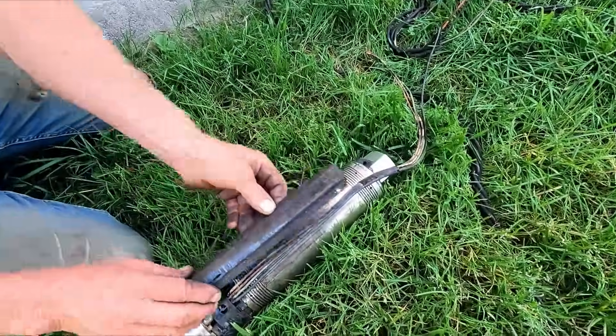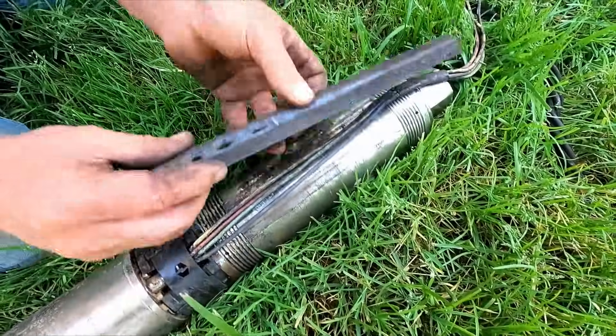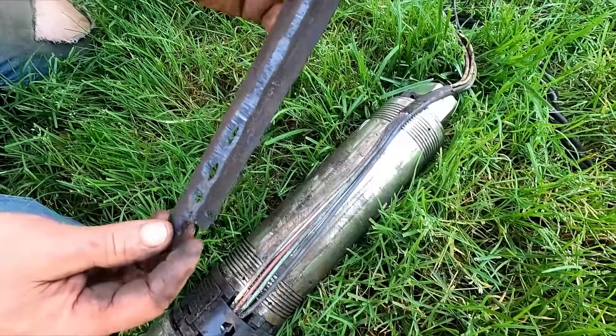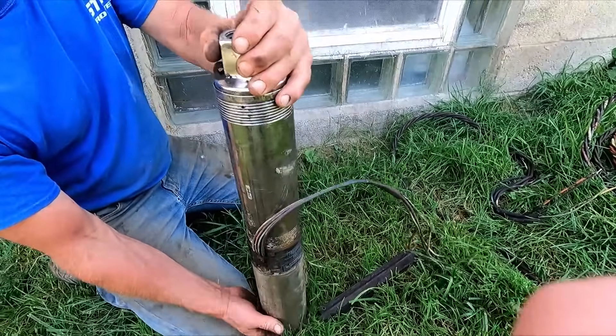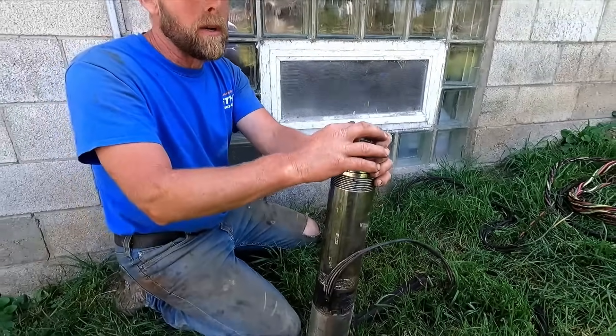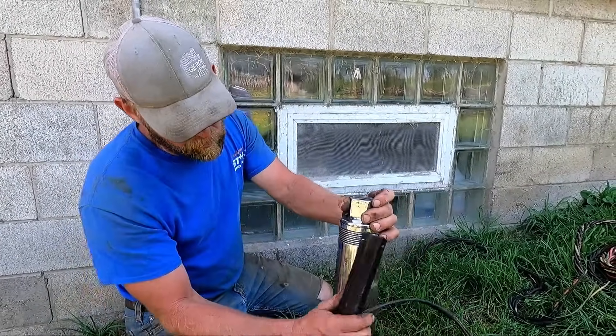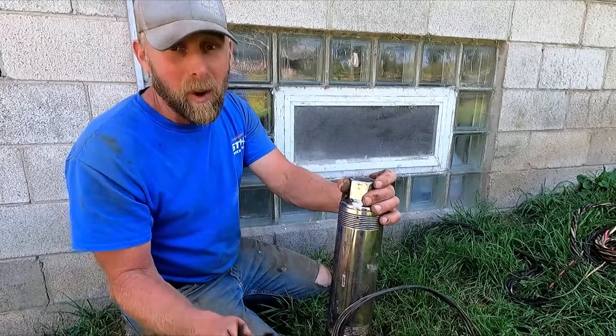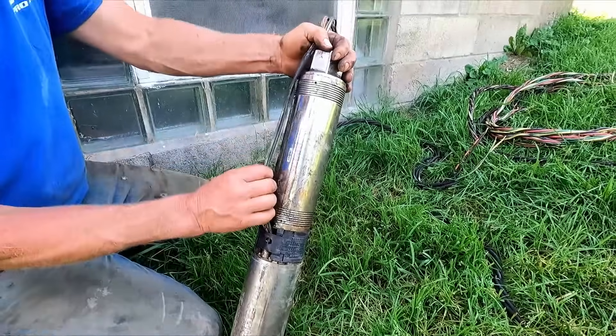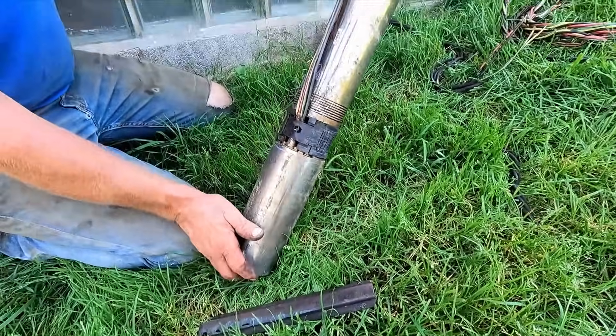I learned something here. This piece of plastic protects the wiring, and they claim every time the pump turns on it spins a little bit — there's friction with the pipe because it's just a plastic pipe going all the way down. He said what happens is this is rattling up against the casing or the rock wall. They thought maybe it wore through to where it hurt the wiring, but after taking everything apart they realized it didn't. They just figured the motor went bad — and you just replace them.